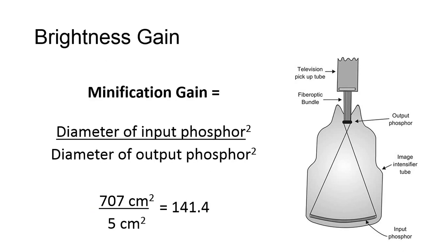Let's talk about brightness gain. There are two processes that contribute to intensifying the image, ultimately resulting in the final brightness achieved and the light image emitted from the II toward the TV camera or other recording devices. These are flux and minification.